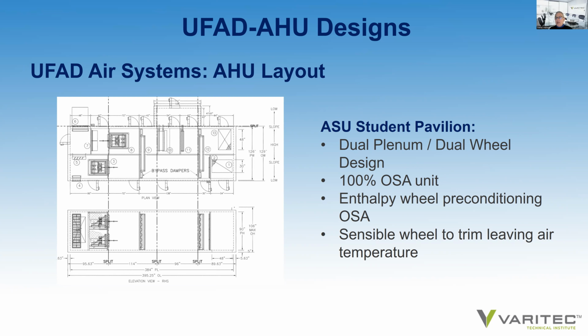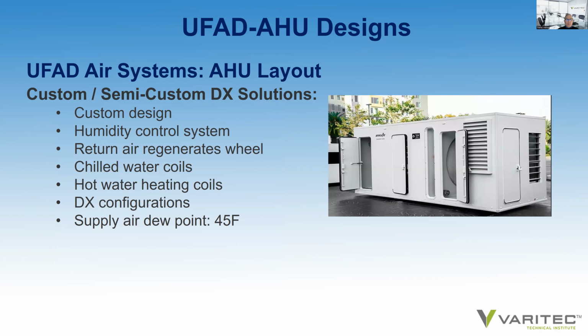That would have to be taken into account regarding energy performance or energy modeling of a system of this kind. There are also custom and semi-custom DX solutions. We have Daikin, we have Annex-Air for fully customized DX solutions that can use hot gas reheat off the cooling coil to provide the appropriate discharge air temperature out of the unit to service a UFAD system.